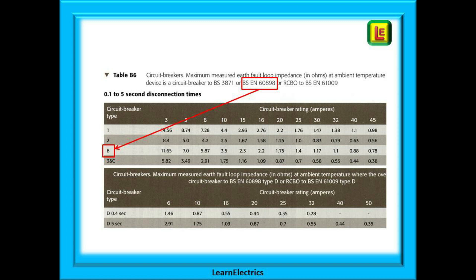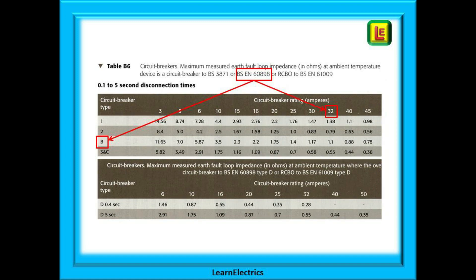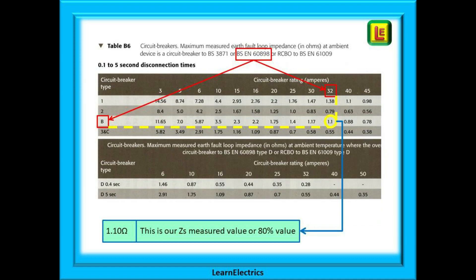Let's look a little more into table B6 in the on-site guide, page 131. Here we wish to select a 32 amp type B BS EN 60898 circuit breaker — the most popular size and type for domestic ring circuits. Find type B along the left edge, then find 32 amps along the top. Following the yellow lines shown on the slide, where the row and column cross we have a value of 1.1 ohms. This is our ZS value.